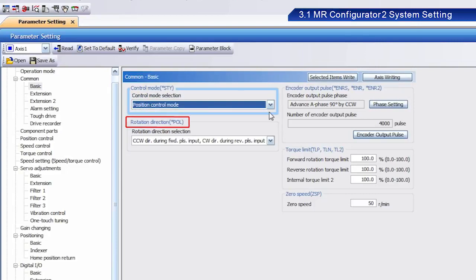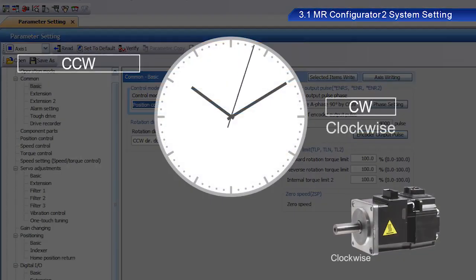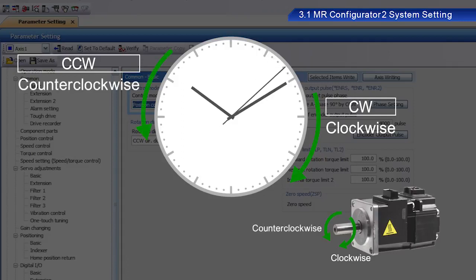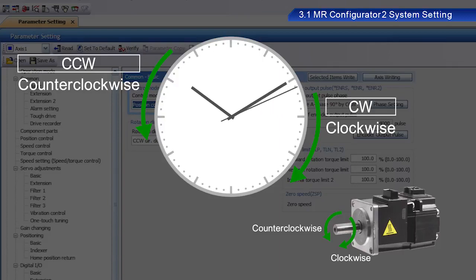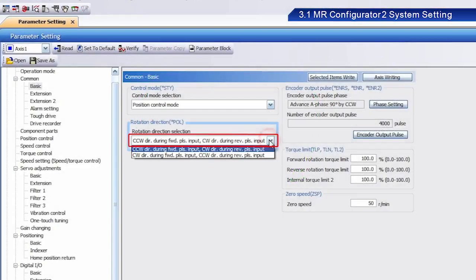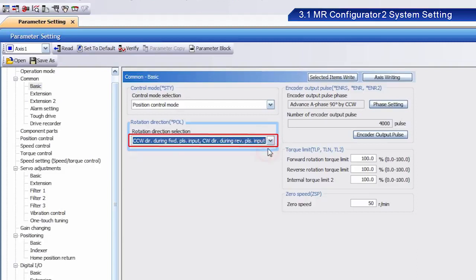Next, select Rotation Direction. CW refers to clockwise, and CCW refers to counterclockwise, regarding the direction of rotation. Select CCW direction during Forward Pulse Input. CW direction during Reverse Pulse Input.